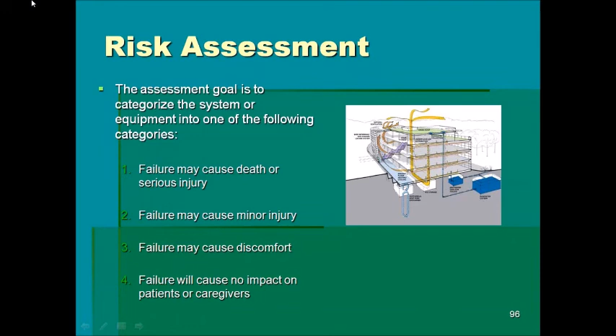That risk-based NFPA code will apply. So if you're going through the electrical section and designing a new dialysis facility in a space that was formerly a storage area, and you determine that failure of the electrical system there would cause serious injury or death, you've got to follow all of the Category 1 requirements for the electrical system as defined in NFPA 99.